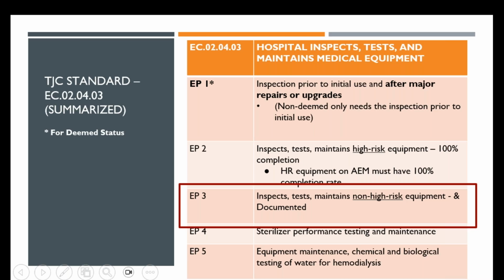But this is the most commonly cited standard for the Joint Commission, and specifically also for SPS sterilizers. So as you prepare, please ensure you're taking a look at your non-high-risk medical equipment PM rates, and make sure that the vendor, if they are providing service on your equipment, that you're gathering those service reports ahead of time. Our site has really found it helpful to complete quarterly audit reports for both imaging and SPS equipment, since we are dependent on those vendor service reports, to just have that documentation available when we're in the Joint Commission survey. So we found that to be very helpful. Scrambling at the last minute, trying to reach out to a vendor and depending on them to not get a citation, is not a good feeling.